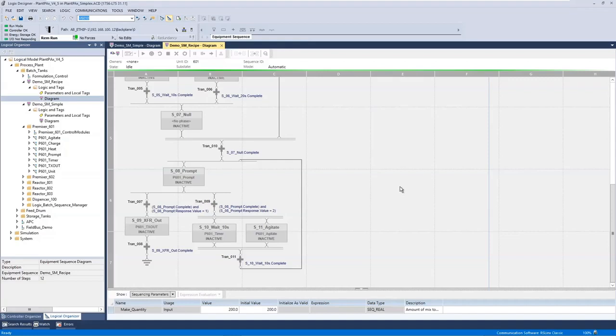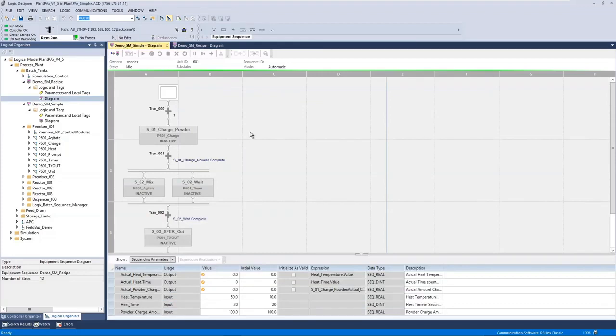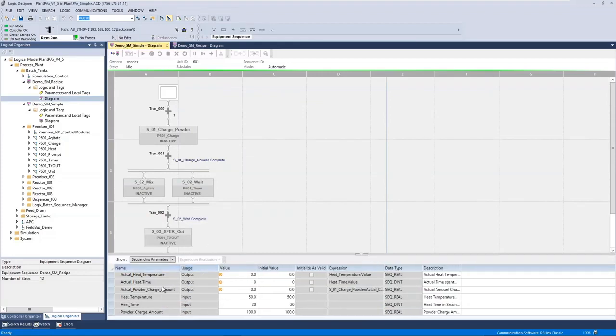These sequences can have recipe values that you can specify. In this example at the bottom you can see we've specified one value and that we'd like the user to specify it when we start the recipe — the make quantity. On our simple recipe we have three values: the heat temperature to heat to, the heat time to heat for, and the amount of powder to charge.